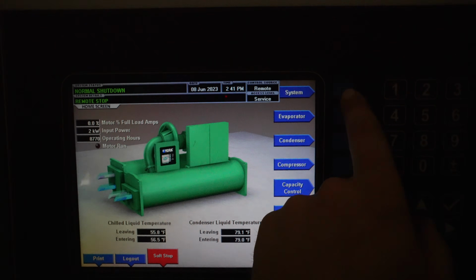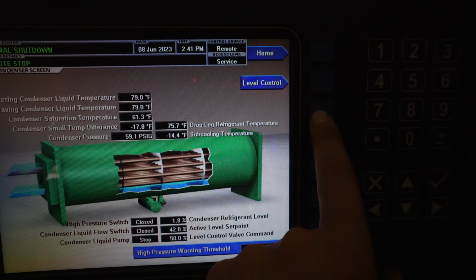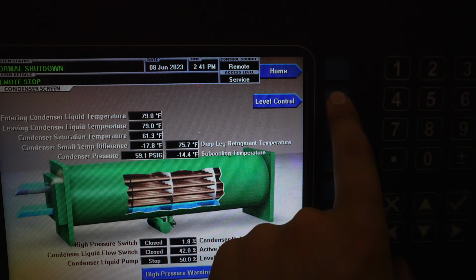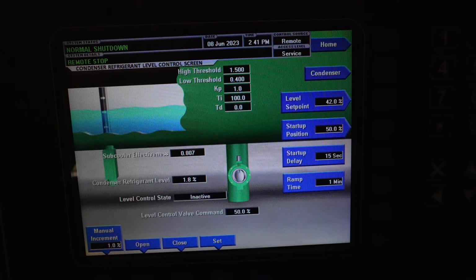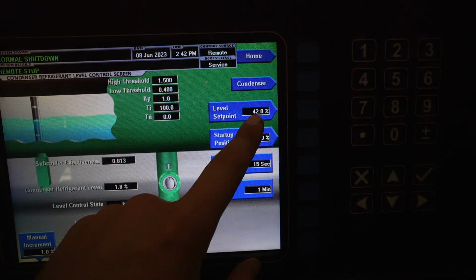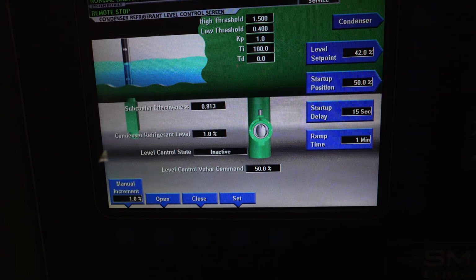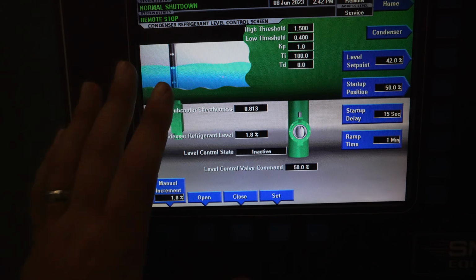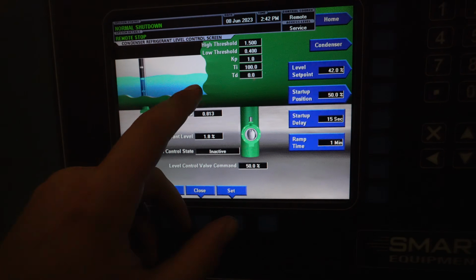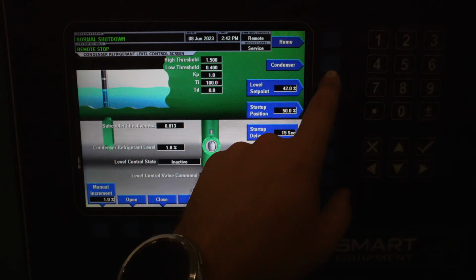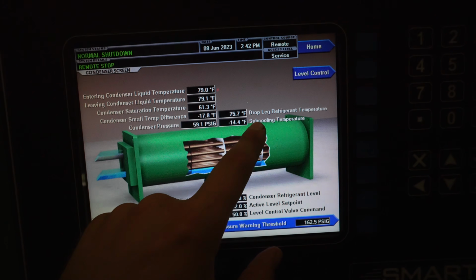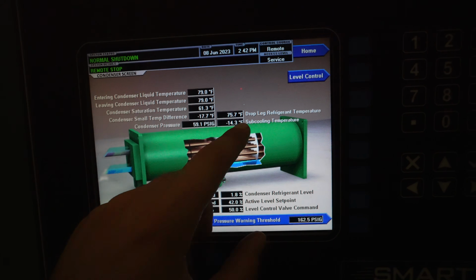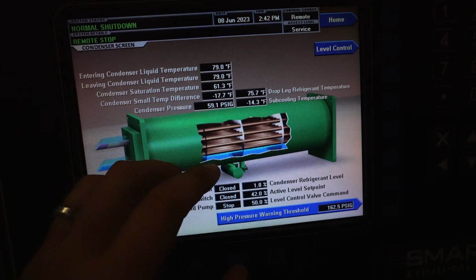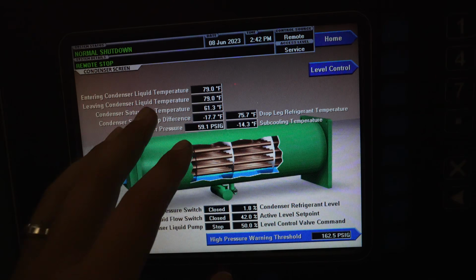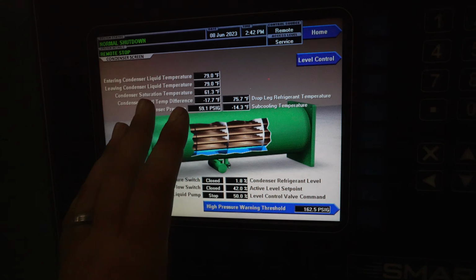So here from the home screen, we're going to go to the condenser, and then we're going to go to level control. Now you need to be in service login for this to work. This was originally at 35%. We were maintaining right at our 35% with absolutely no issue. And we were also pushing a 10-degree subcooling temperature, which is a lot. 10 degrees on this machine for me is a lot.